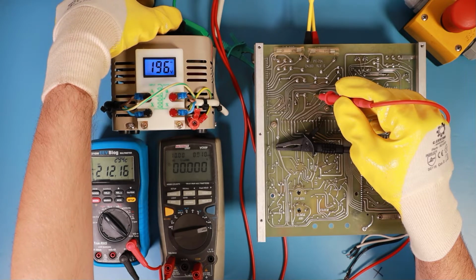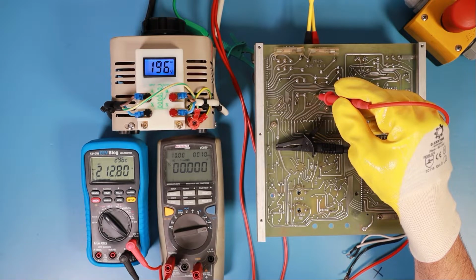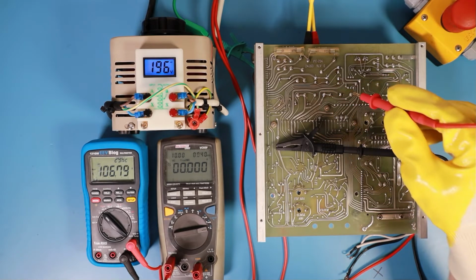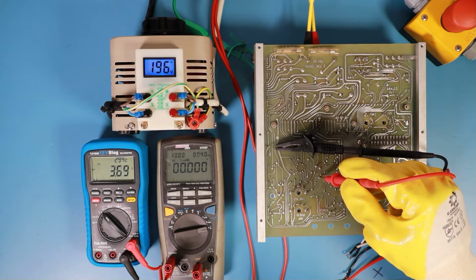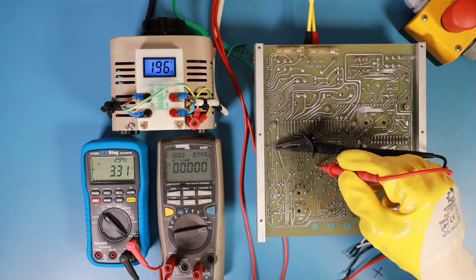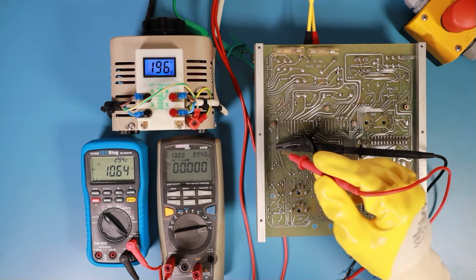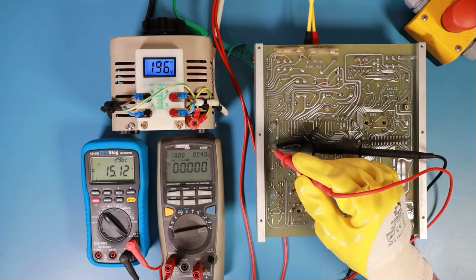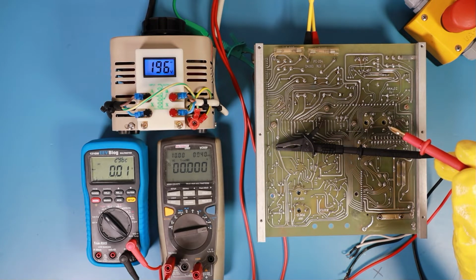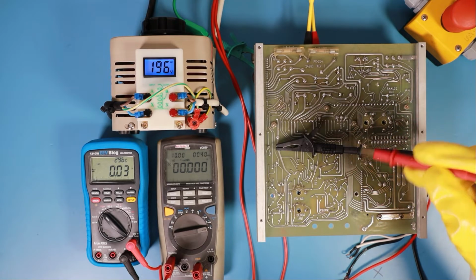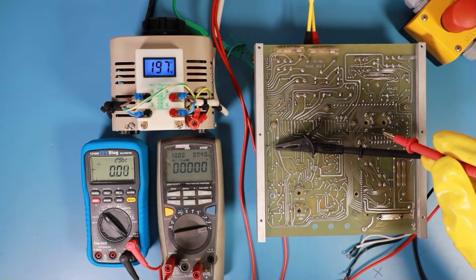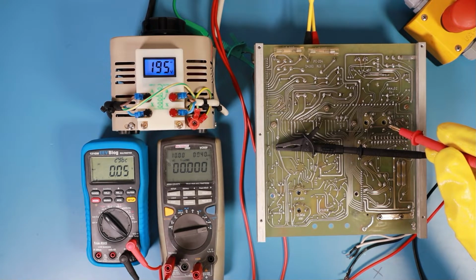Okay, we are at 210 volts on the capacitor and only around 200 volts on the input voltage. So we have 3.7 volts for our 3.6 volt voltage range or power line. We have plus 15 volts spot on. We have negative 15 volts and they are a little bit off. So I think we should expect to have no wrong voltages which will kill our device or kill the rest of the electronics.